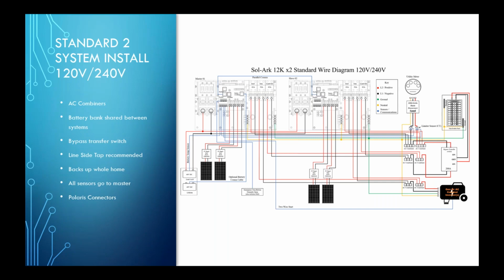But yeah, without further ado, we'll look at this 120/240 double system setup. The main difference here, and the great thing about 120/240, is that it is really just paralleled. So all the AC inputs are paralleled to each other, hence why you see a lot of AC combiners. In this case, we are showing a whole home backup with two systems. A lot of the time you can get away with two systems for a 200 amp service.